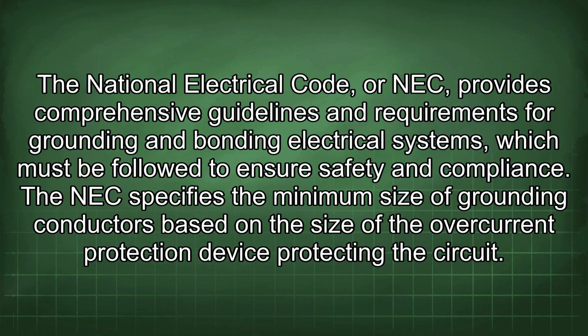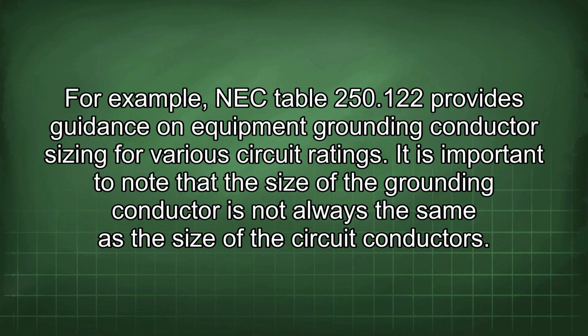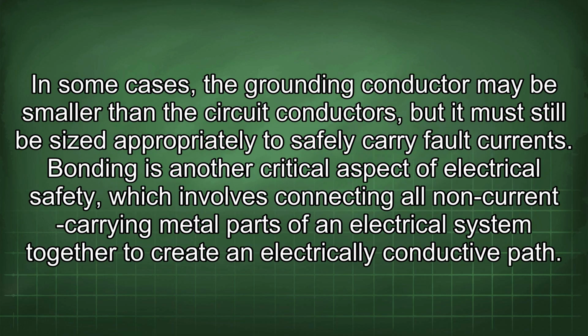The NEC specifies the minimum size of grounding conductors based on the size of the overcurrent protection device protecting the circuit. For example, NEC Table 250.122 provides guidance on equipment grounding conductor sizing for various circuit ratings. It is important to note that the size of the grounding conductor is not always the same as the size of the circuit conductors. In some cases, the grounding conductor may be smaller than the circuit conductors, but it must still be sized appropriately to safely carry fault currents.